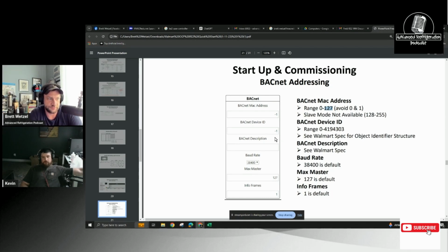They don't on the SC3s. If you look at them, your master's 7, and then every one after that is a ridiculously high number. So they're doing a similar thing, where the range for the primary controller is from 0 to, in this instance, 0 to 127, probably bumped up for future expansion. I think it's a generalized thing from what I've seen. So 0 to 127 means we have the capability for 127 primary controllers, and then we have the availability for this many slaves, you know what I mean? No, that makes complete sense.